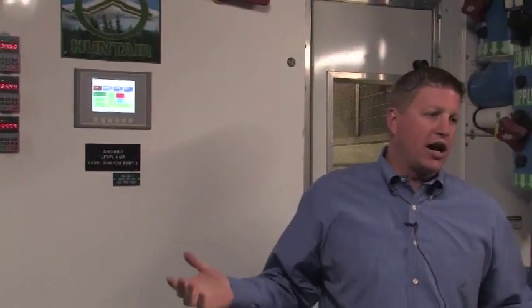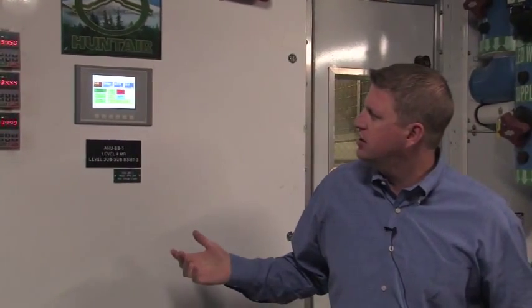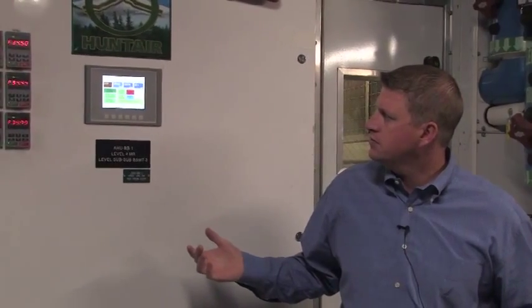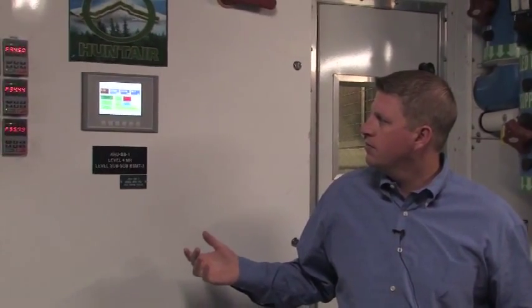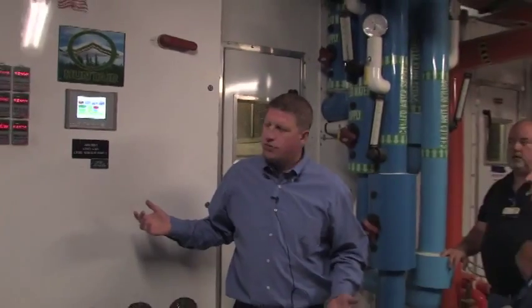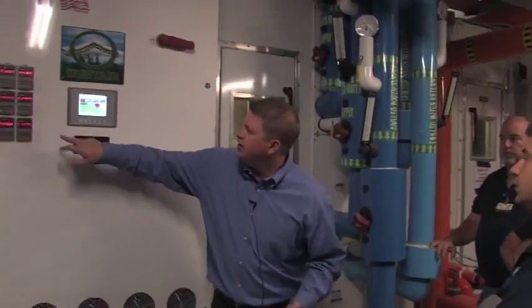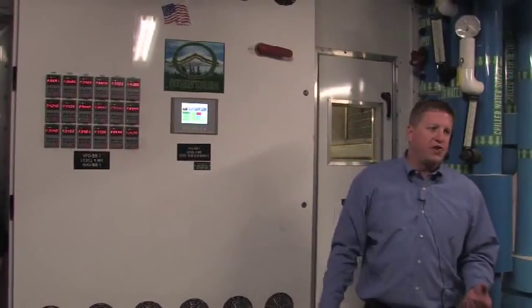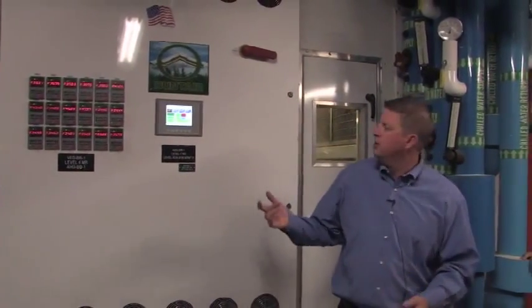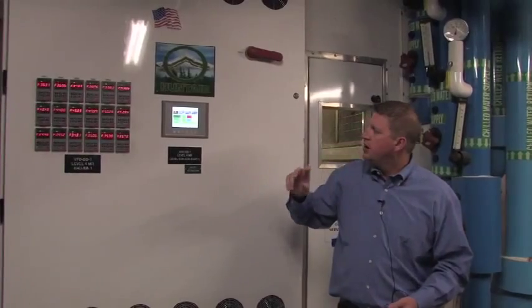It's going to shut down. It's going to lose its signal. It's basically just letting you know what mode it's in at that point. Exactly. So I'm in hand right now. You're going to see all these drives go to 15 hertz here because that's the minimum set point. So it's shutting down.